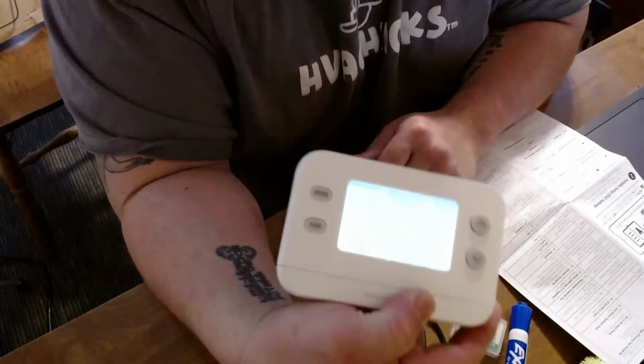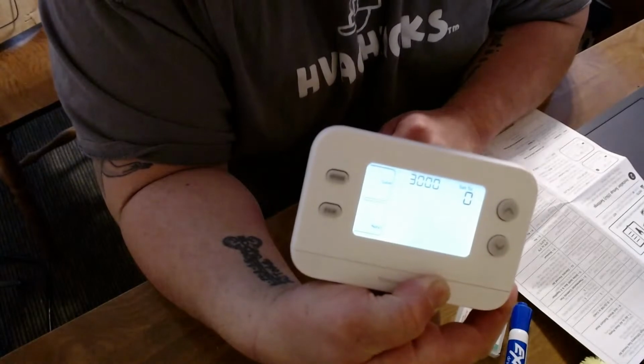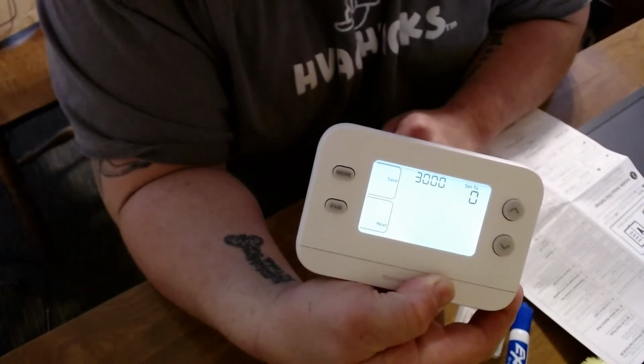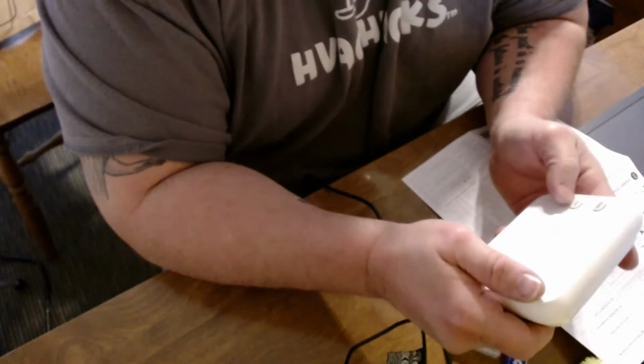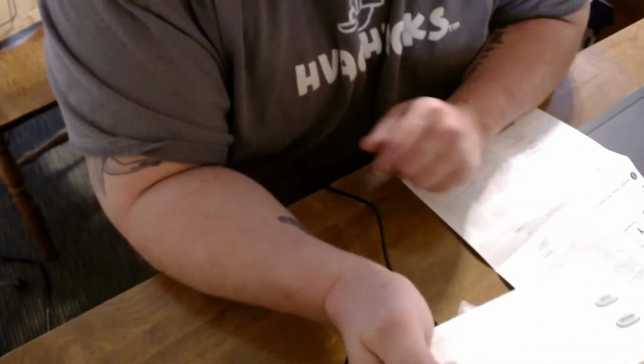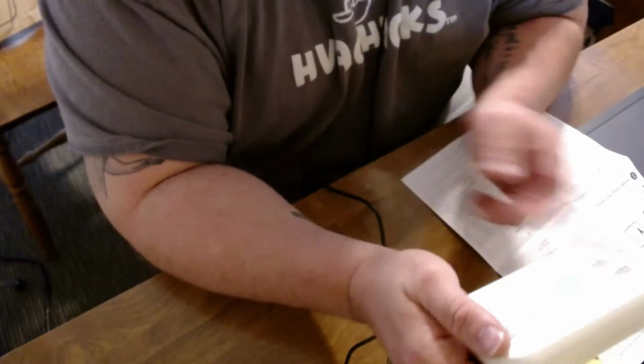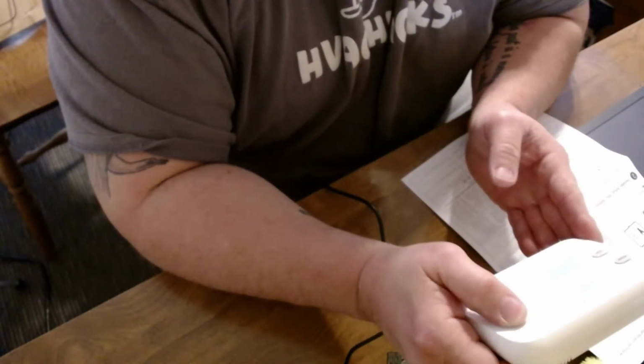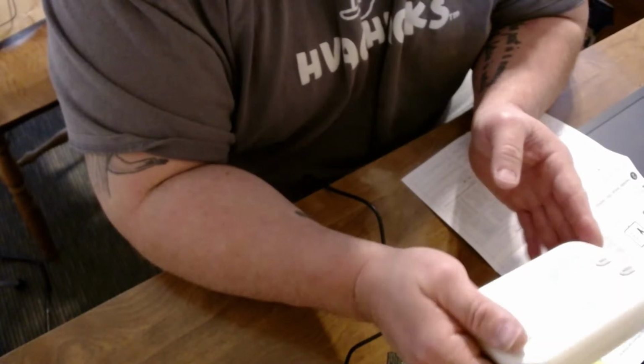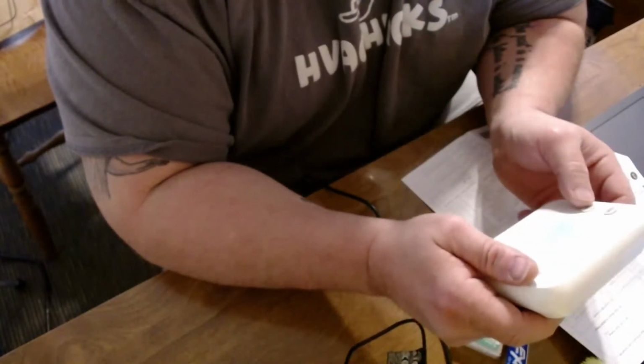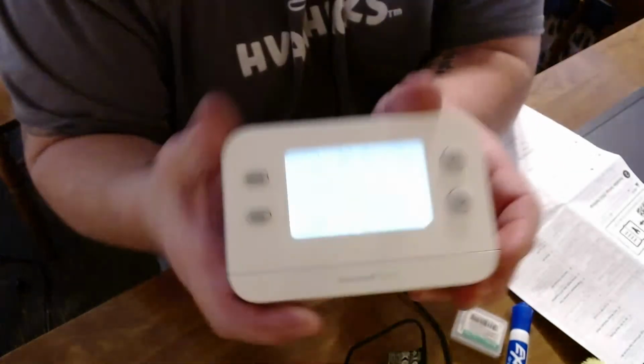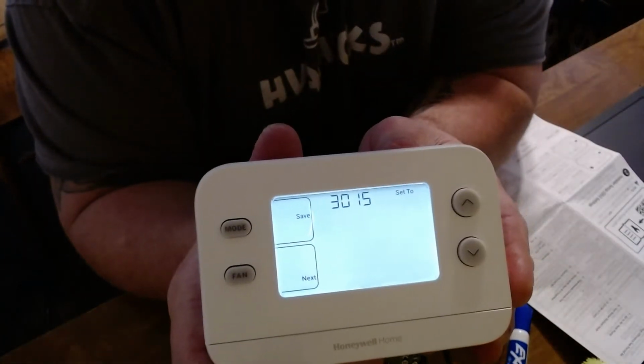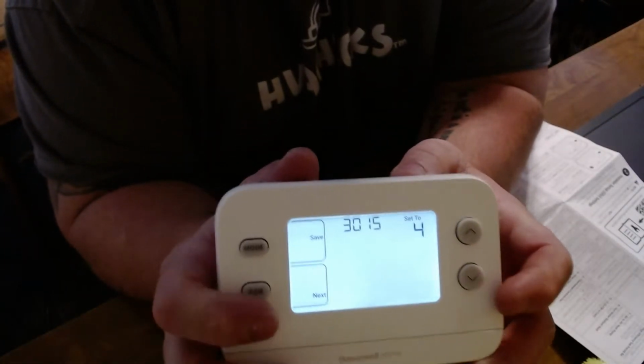3000, system changeover, auto or manual. Now, I like to give my customer the auto ability, so I set it for auto. 315, differential. So the difference between your heating and cooling, I like to set those to 4 degrees. That way you've got a good dead zone. So 315, set for 4. All right.